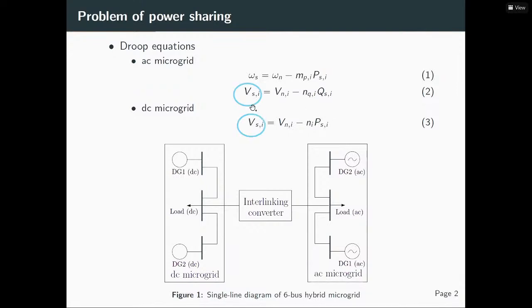Since Vs is different for different buses, Vn minus Vs will be different for all the buses. This will result in NQ into Q terms not being equal for the various DGs. Why NQ into Q being equal is important is that the value of NQ, the droop coefficient, is inversely proportional to the rating of the generators, the size of the generators. So we expect that the smaller generator should give proportionally smaller power.